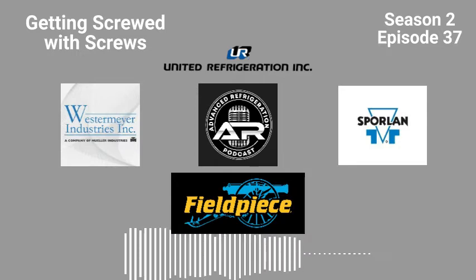The only nice thing here is if somebody wasn't stupid and left the whole filters on. You're supposed to have one filter on, one filter off. So there's two filters, a spare and a primary. That way, when one plugs in the middle of the night, you could turn on the other one, valve off that one, change it, and go on your way. It isn't going to take the whole rack down.